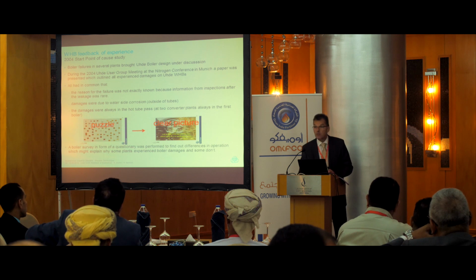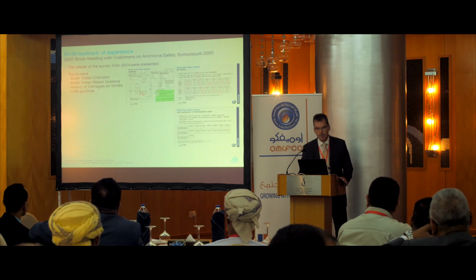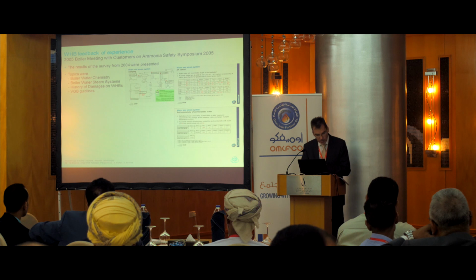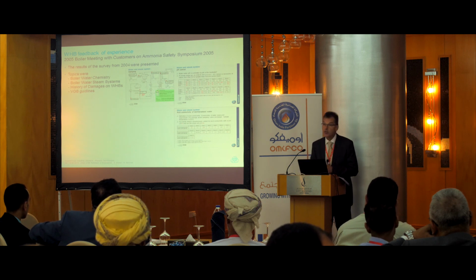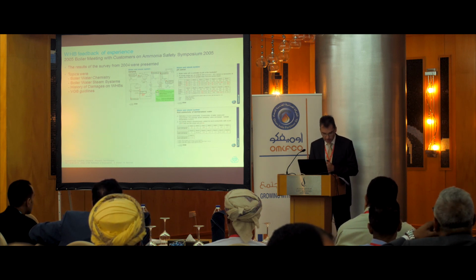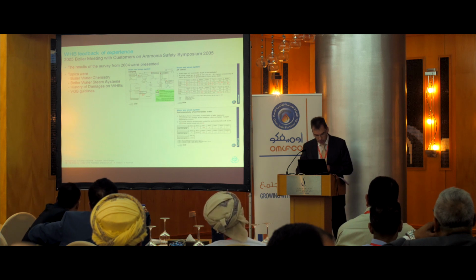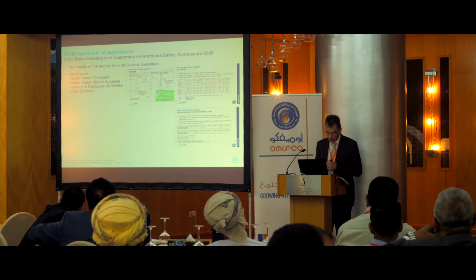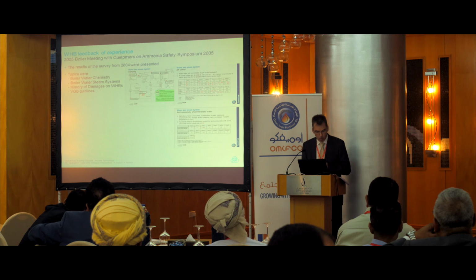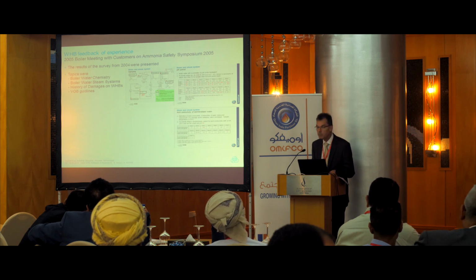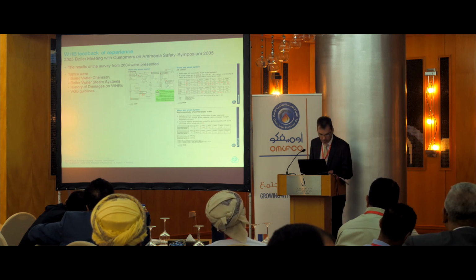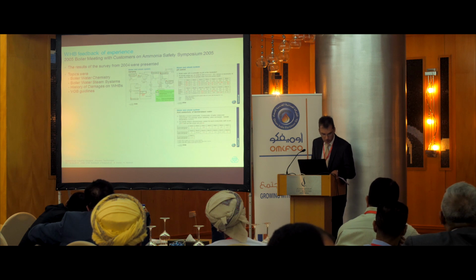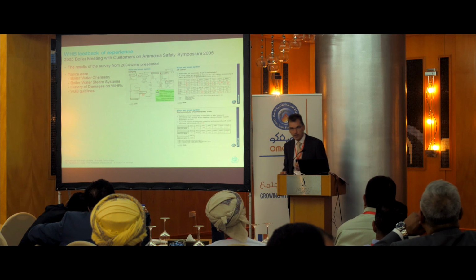What have been the results of this questionnaire? In 2005, a boiler meeting was held at the Ammonia Safety Symposium, presenting the results of the questionnaire, proving that data were not always in the optimum range according to our VGB standard. VGB is a German standard regarding feed water, boiler water, and steam quality in power plants. We base our quality rules on this standard.